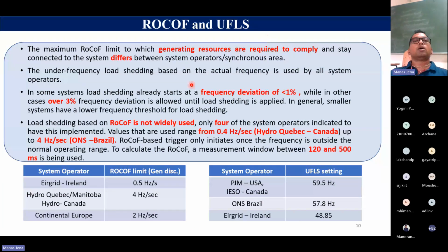Many operators around the world use ROCOF and UFLS as a last resort, as special protection schemes, to knock out loads or to knock out generation. The maximum ROCOF limit to which the generating resources are required to comply and stay connected to the system differs from operator to operator. For example, you can see the left side table. The Irish operator uses a ROCOF of 0.5 hertz per second for generator disconnection. Hydro-Québec uses 4 hertz per second. Europe uses 2 hertz per second.